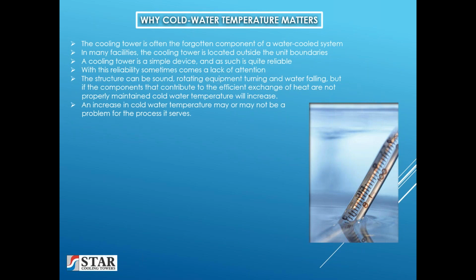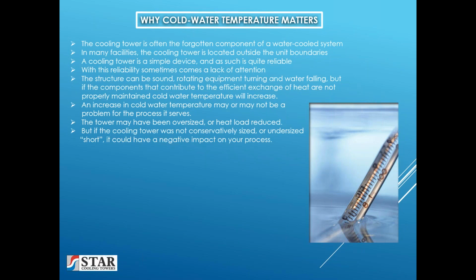An increase in cold water temperature may or may not be a problem for the process it serves. The tower may have been oversized, or the heat load had been reduced over the years, reducing the load on the tower. But if the cooling tower is not conservatively sized, undersized, it could have a negative impact on your process. Particularly the older towers that were built prior to acceptance testing and performance guarantees were intentionally built short in the competitive environment. It was not unusual to see a cooling tower that maybe was 80% of design, but because of the conservative nature of the design conditions, it went unnoticed, but it would be on the borderline.